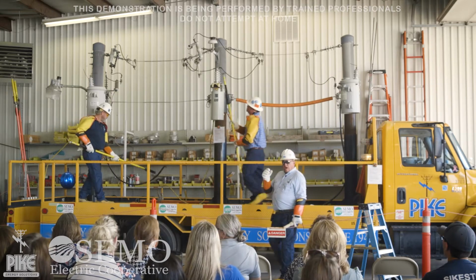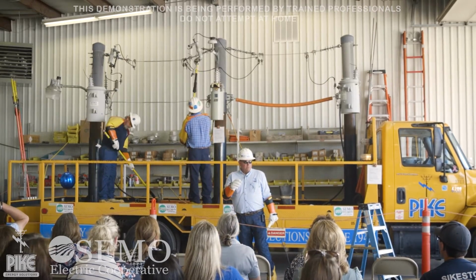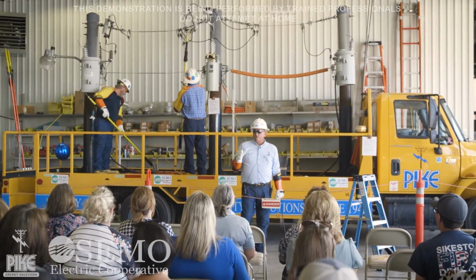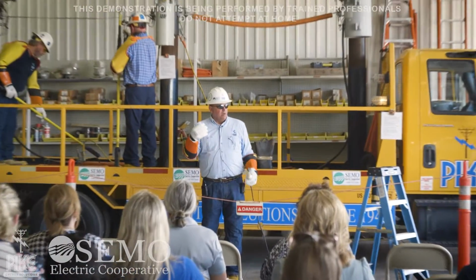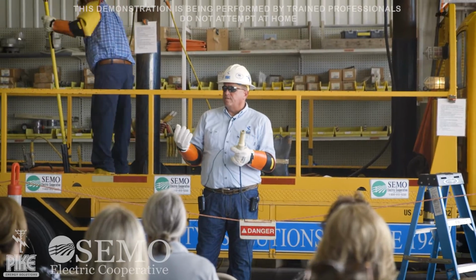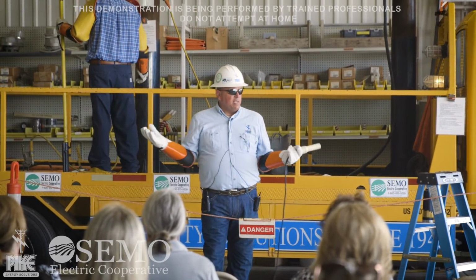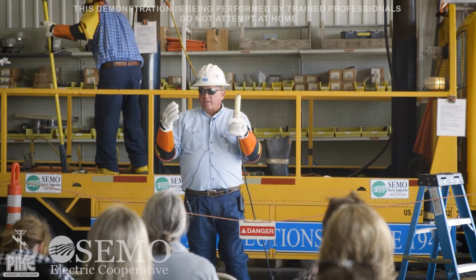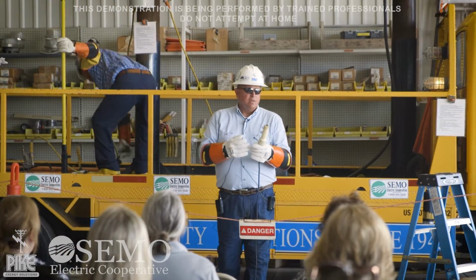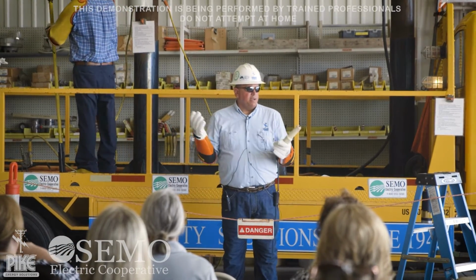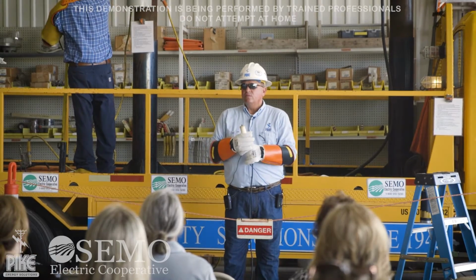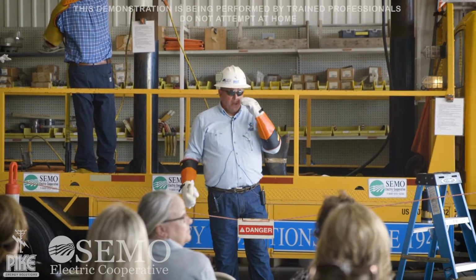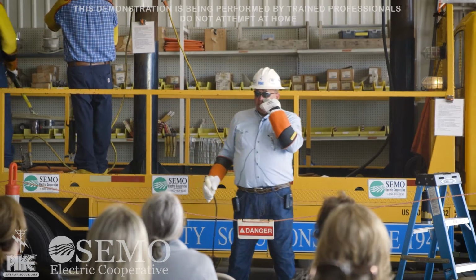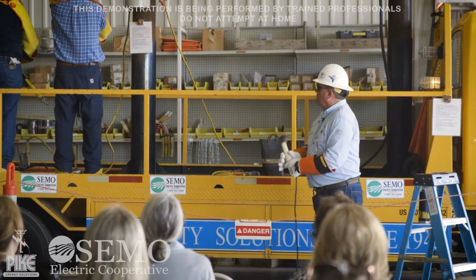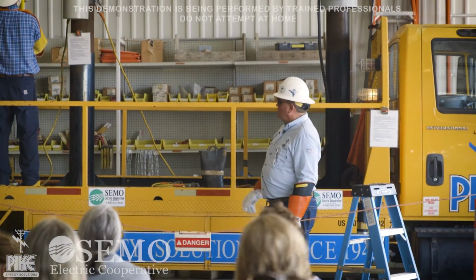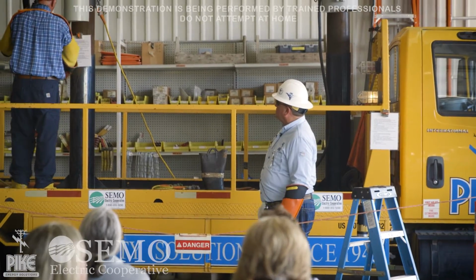Now that's not an easy fix typically, is it? You guys that do line work back there know if it's a loop feed, you got to go through there and figure out where the open point is. You gotta isolate this cable. You gotta make sure that open point can tie together. You go back to where the problem is. You gotta stand it off, test it, ground it. Then you gotta spike it, cut into it, then make the termination. It takes a little bit longer than the transformer. Always important to make sure we get our locates.